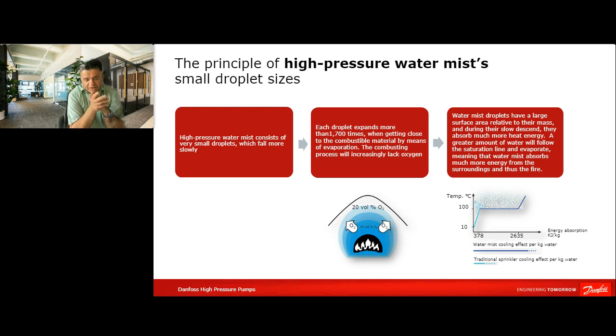The next one is the cooling effect. What does it mean? Whenever you have the small droplet sizes of water mist around the fire source and the flames, and temperatures reach those droplet sizes, they vaporize from water to steam, and this change of condition takes a lot of heat energy out of the fire. So at the fire source, you cool down or reduce the temperature enormously, and this is the second major effect of the high pressure water mist. So on the one hand, the inertizing or oxygen displacement; on the other side, the cooling effect.